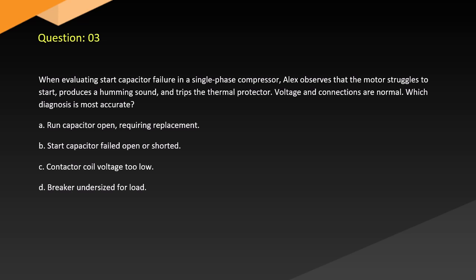A. Run capacitor open, requiring replacement. B. Start capacitor failed, open or shorted. C. Contactor coil voltage too low. D. Breaker undersized for load.